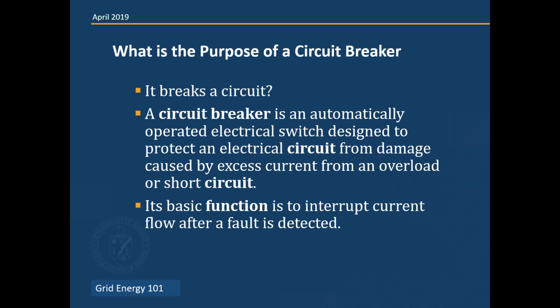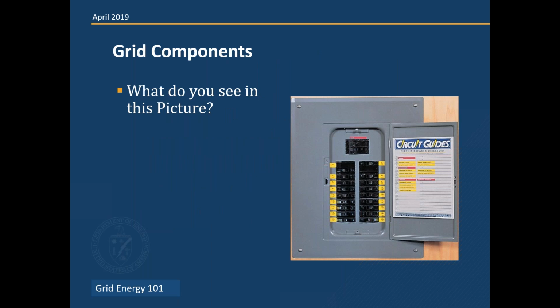So what is a circuit breaker? What's its purpose? It's as simple as it breaks a circuit. A circuit breaker is an automatically operated electrical switch designed to protect some electrical circuit or equipment from damage caused by excessive current from an overload or a short circuit. The basic function is to interrupt current flow after a fault is detected. Next slide, please. So here's something that's very familiar. This is the panel at my house. So at the top of the gray box there is my main circuit breaker, and then below it are the different circuit breakers that are like little mini distribution circuits in my house. And so if I open that breaker on the top, the very top one, my house is de-energized. Next slide.